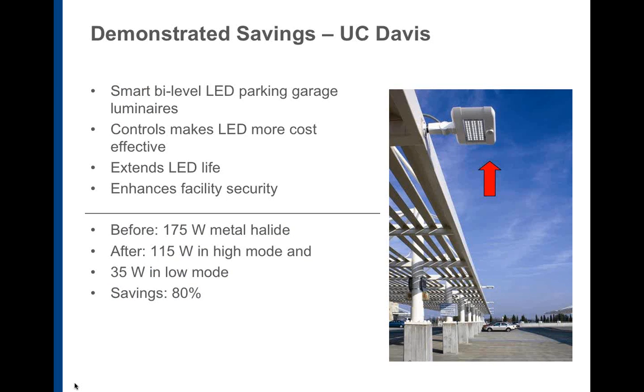So in this case, we have sensors on the unit, and these are not networked. This was an early test that's been in place for over a year and a half now. We had a 175 watt metal halide before, and after, in high mode, 115 watts, but that drops down to 35 watts in low mode, and that's how we achieved that very high savings number of 80%.